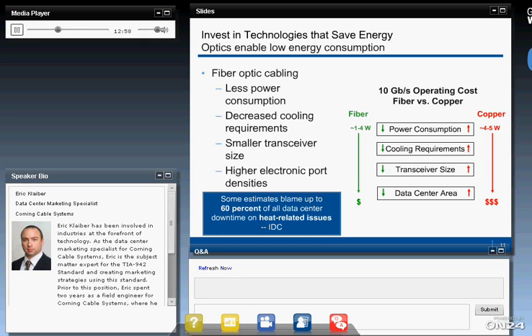Compare that to fiber. Typically on a short multi-mode run, you're looking at around 1 watt per port. For single-mode fiber, where you're going building to building or up several stories, distances further than multi-mode can handle, the lasers are more powerful and require more power to operate, so that's where you see that 4 watt figure come in. But that's not typical—multi-mode is typically used within the data center itself because of its distance limitation, so you use the VCSEL, which has much lower power wattage than copper.